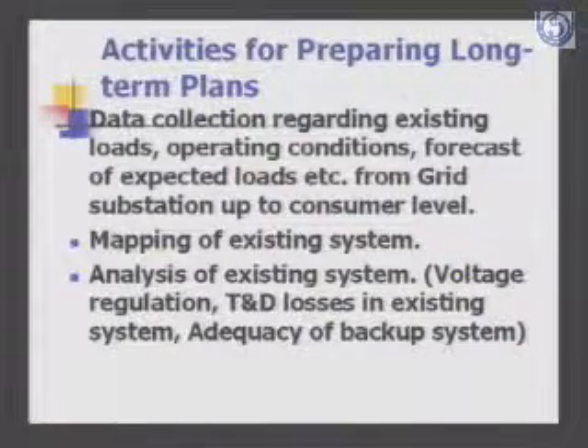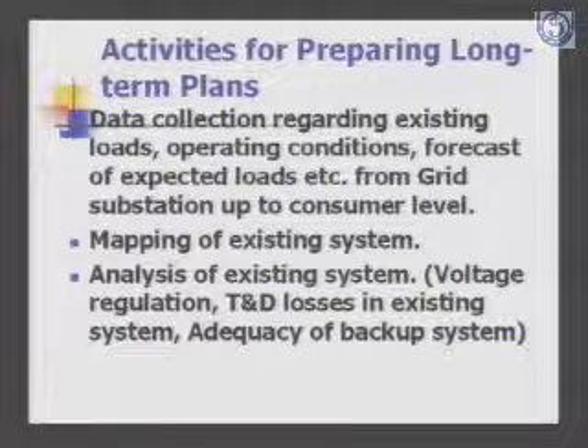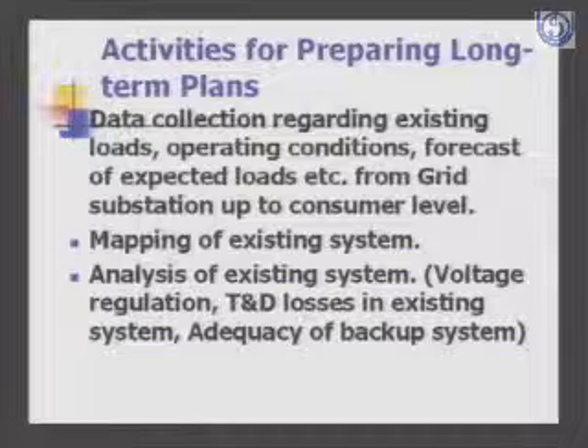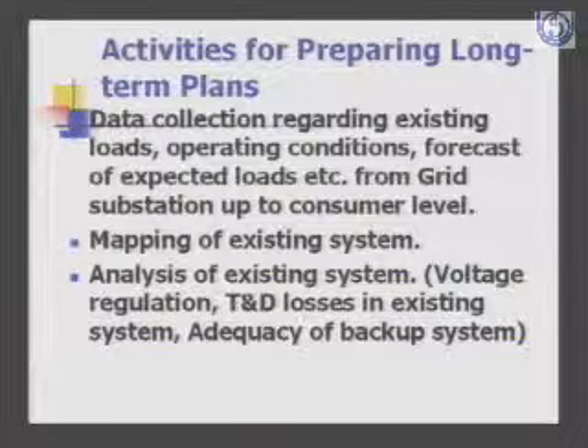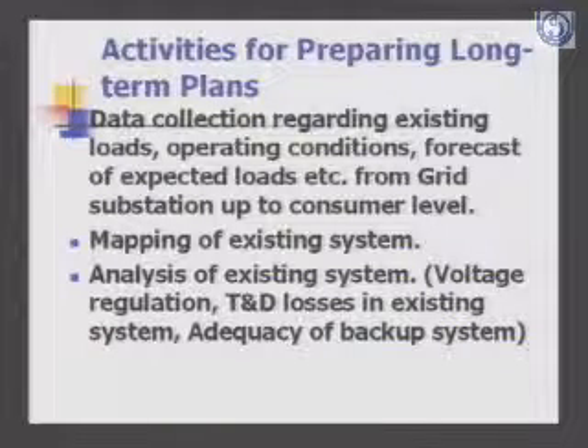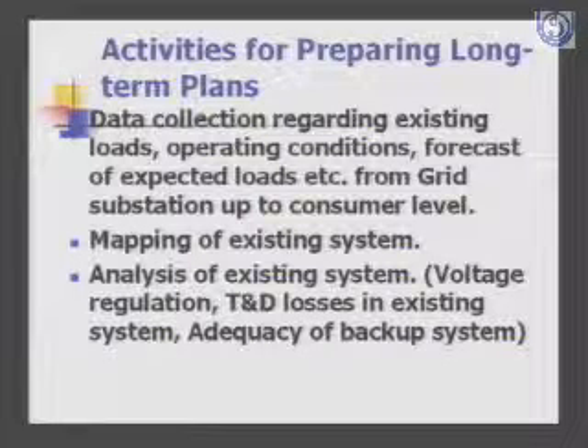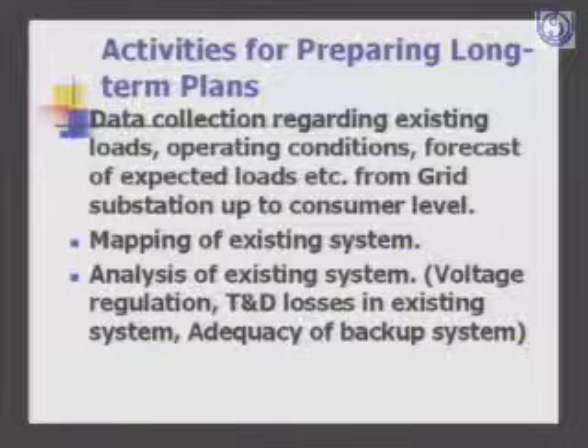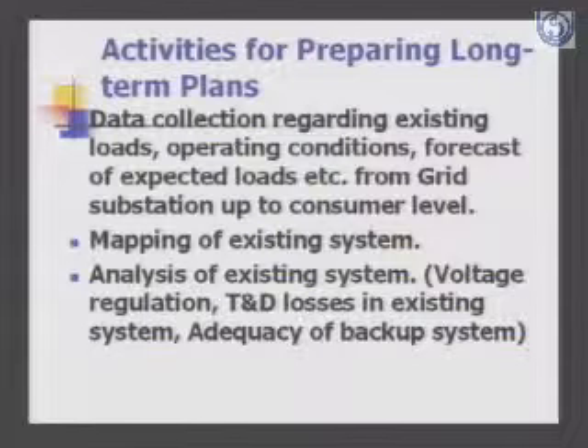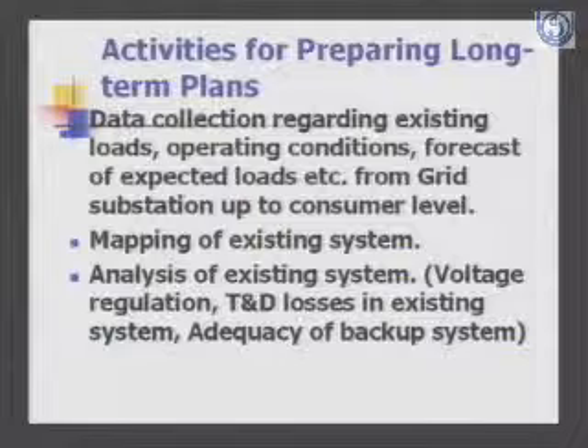So the activities required include mapping of the system. Documentation of the distribution system is the most crucial part in preparing the long-term plan, and we do not have data for distribution systems. What happens is that the data for the distribution LT lines and service connections is only with the lineman or JE. But to plan a system, you should have all the data, right from the consumer level up to the 33 or 66 kV substation, at a central level. It may be available in the sketchbook or in the minds of the JE, but it is not available to the planners.